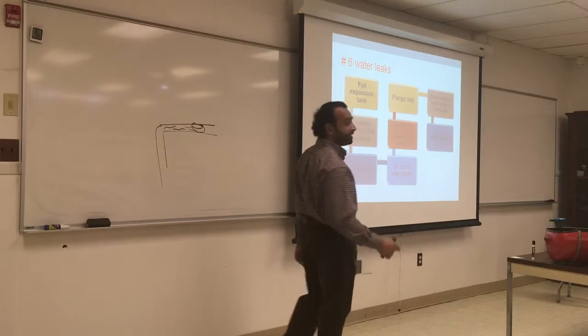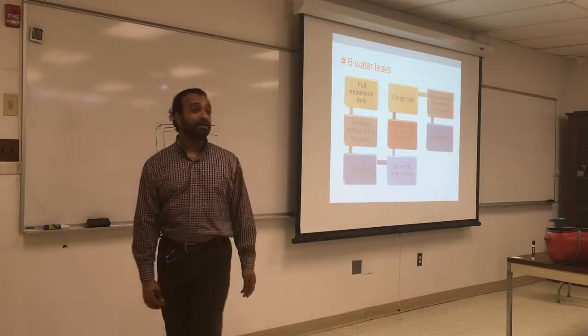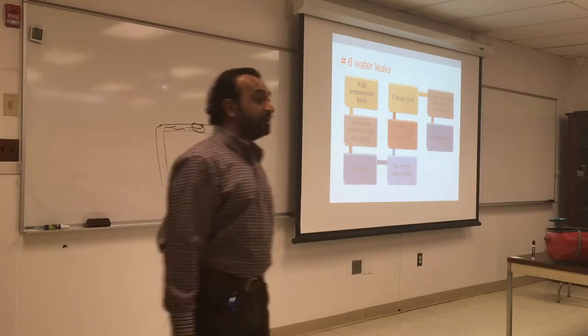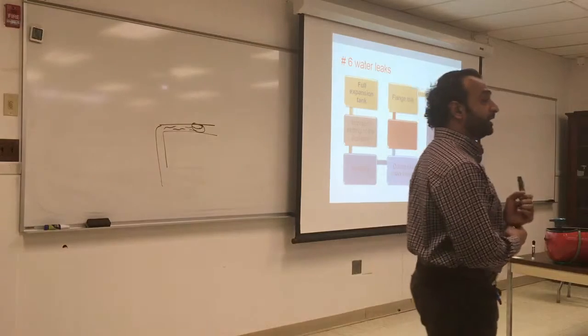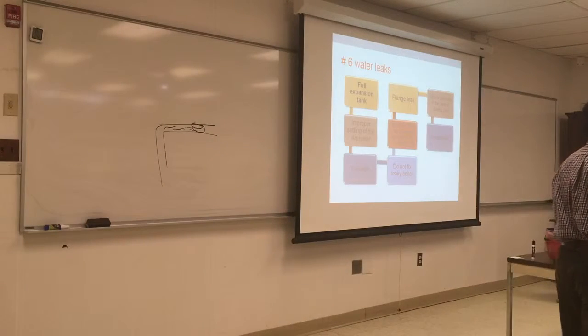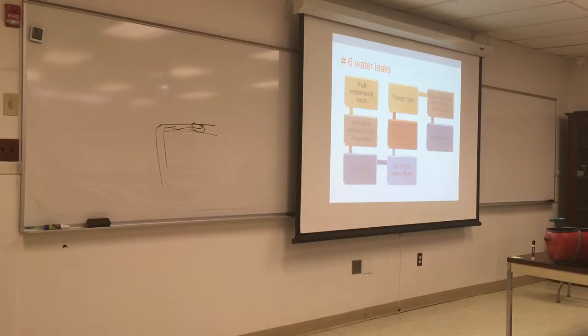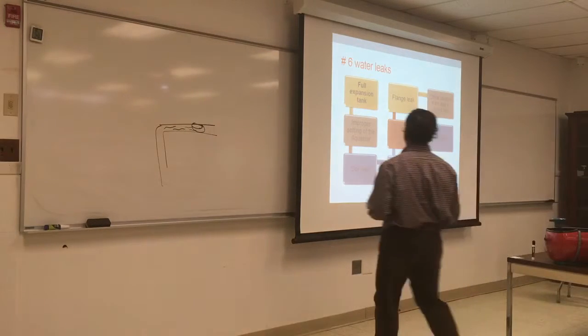Improper setting of the aquastat, as we said: if you put it too high, the water expands too much. The system was designed for 180, and suddenly it's at 200. Yeah, that's what they want. The water setting is too high, and what happened? The water will expand more than it's supposed to, and eventually it will leak. So if it's at 180, make sure it's set at 180.